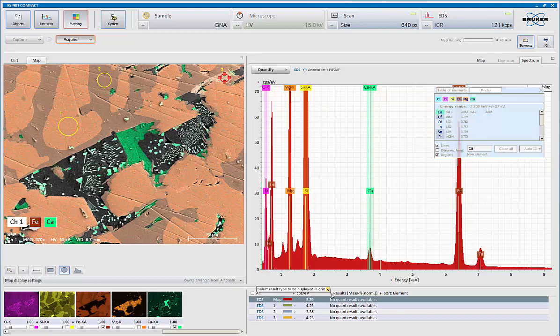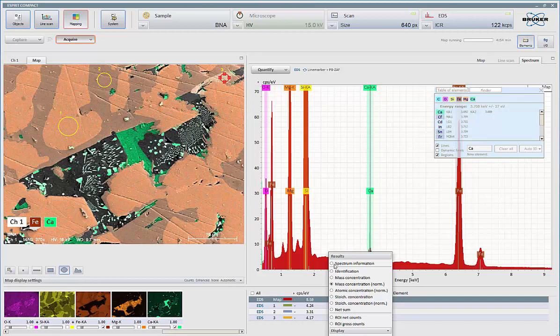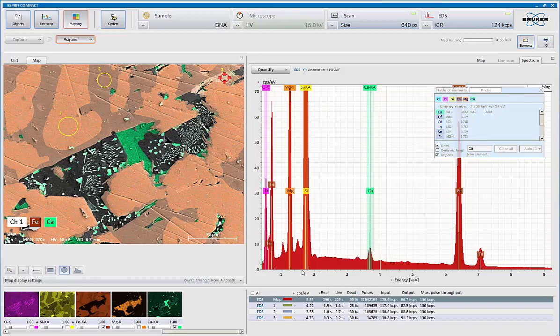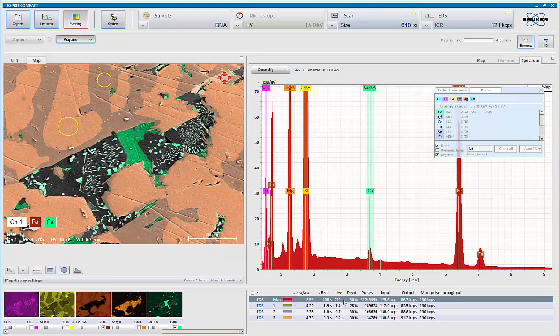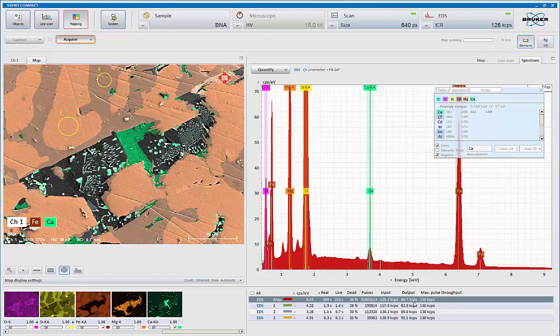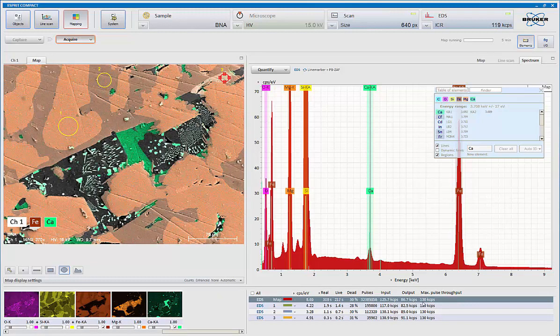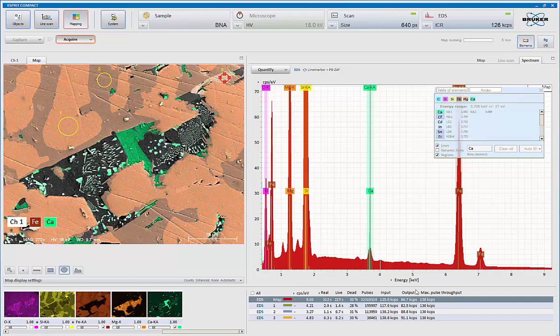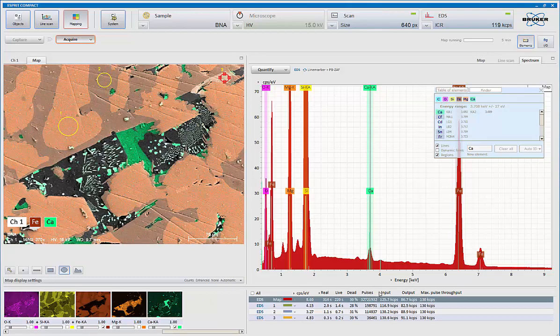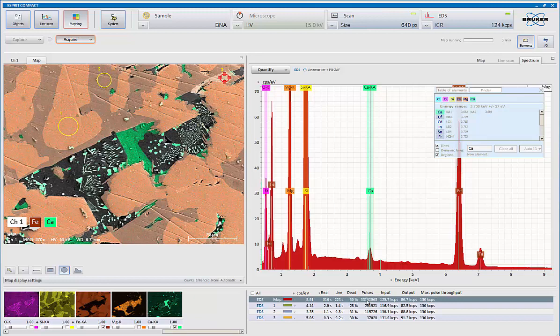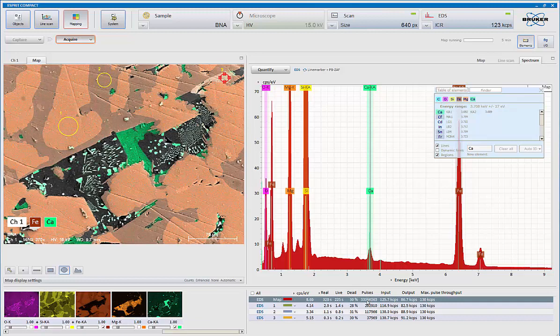Utilizing these tools down here where it says results, remember, any place you see a triangle or an arrow, there's a menu. So if I click on that, here's all the things I can look at. Right now I want to look at the spectrum information. And what this shows me is how long I've been collecting total, my dead time, total number of counts within the map, and also that spectrum, what my input and output count rates are, and then what process mode am I currently using. Right now we see we've got about 32 million counts, which is pretty good.